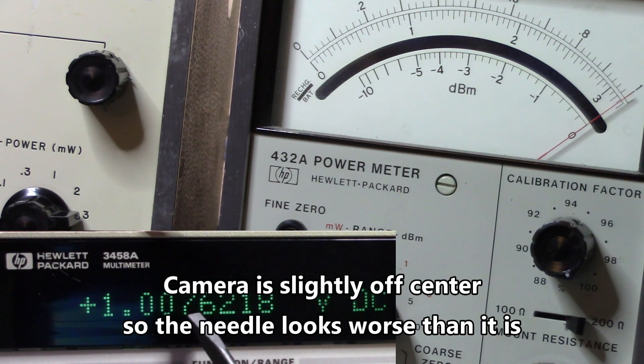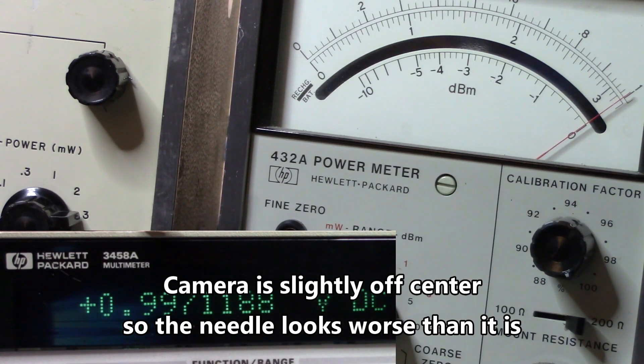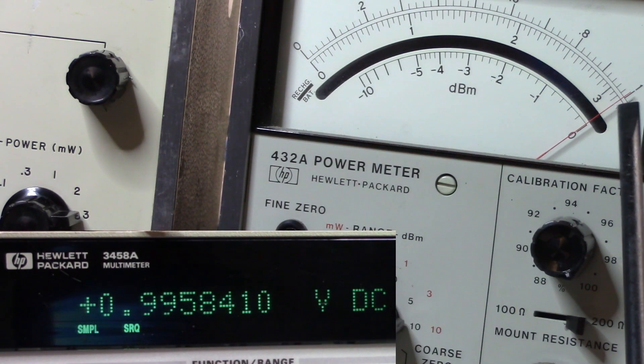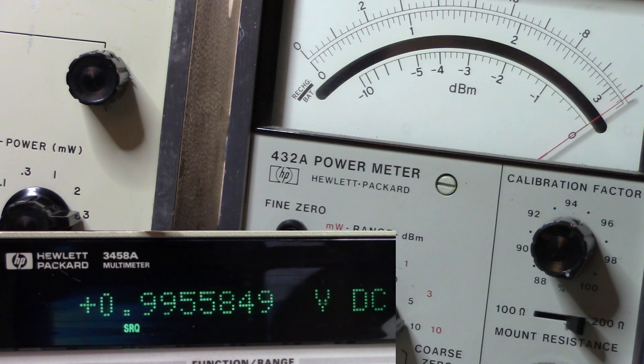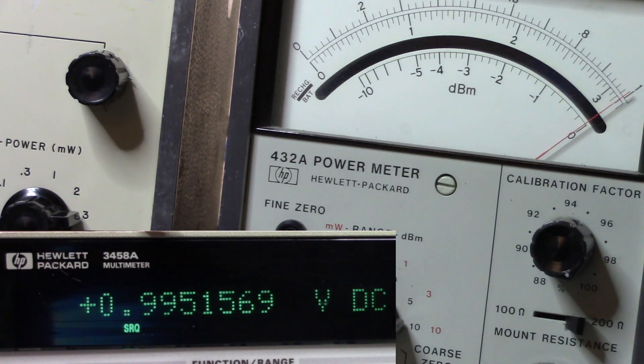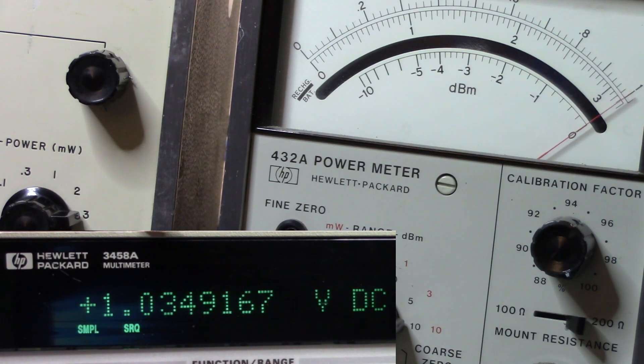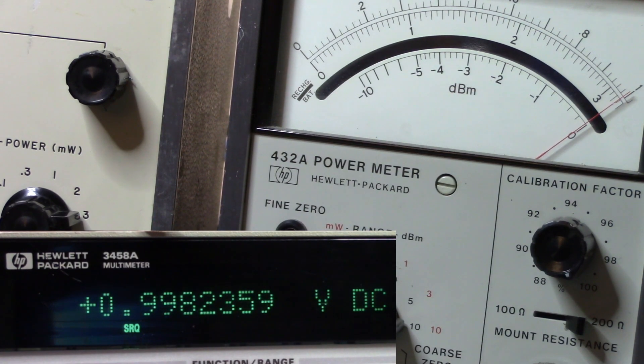As we can see here we're getting 997 millivolts, that's in range. We're supposed to be here on a one plus or minus half a deviation. I'm getting half a deviation there. So overall we'll declare that good.